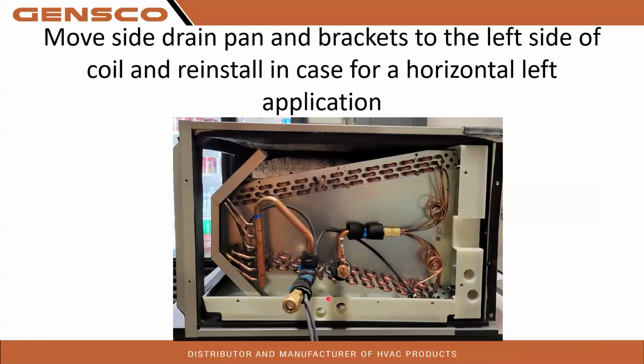Once you get them all flipped to the other side, you'll go ahead and put the drain pan and everything back in. Put the bottom pan back on, and you are now set up for horizontal left. So put your metal cover back on the front of this thing. I didn't do that for illustration purposes, but that metal cover that was on it originally will go back on and in place, and the whole thing will just slide back in. You'll put your clamp bracket back down here and screw that in place if you're done.